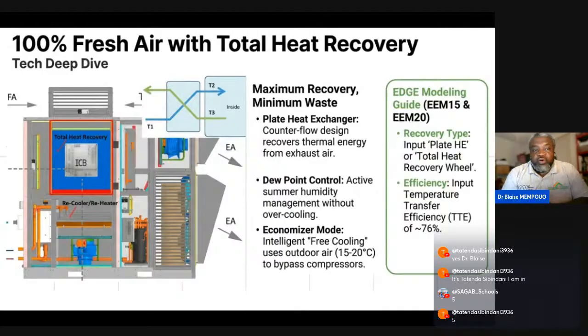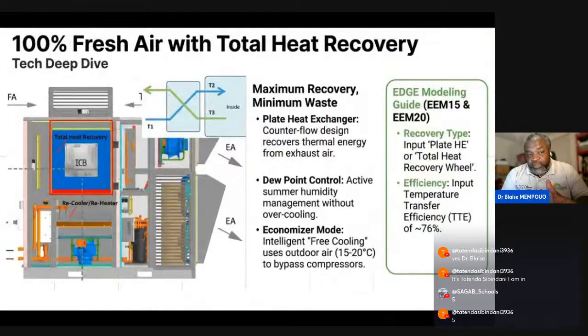For free cooling, 100% fresh air, as mentioned earlier, is measure EEM15 and EEM20. If you want to model that through the edge, you use free air cooling, crossplate heat exchanger and dew point control. That can easily control humidity in summer, since humidity is controlled only in cooling mode. The economizer provides free cooling: when the outside air is appropriate, the system stops cooling and stops using the compressor. The compressor doesn't cool anymore, it just provides free cooling in the building. That's the advantage.